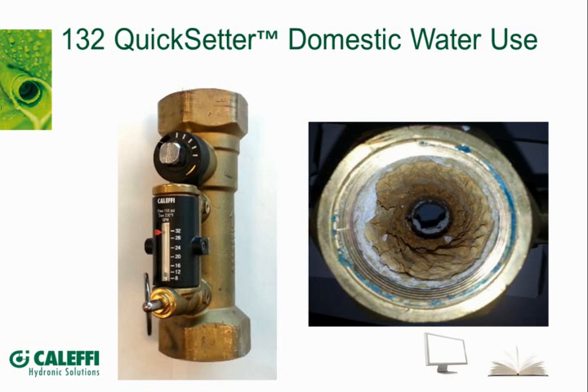And so if an engineer was simply on a hot water recirc, just trying to overcome the temperature loss in the pipes going up to the fixtures alone, that calculation might result in a fluid velocity a little bit less than optimal as it relates to scaling. Well, let me think here for a second. Higher fluid velocity is going to wear the pipe away faster. You'll have more pipe corrosion if it's an aggressive water, but you'll help limit the scaling if it's a scale-forming water. Yeah, that's like a catch-22 question.